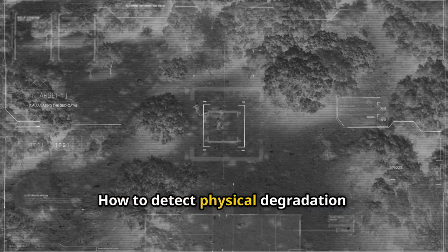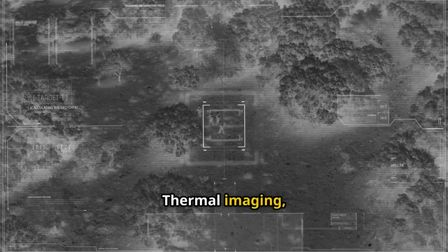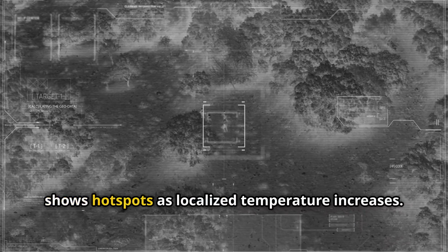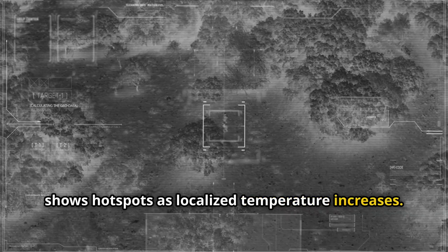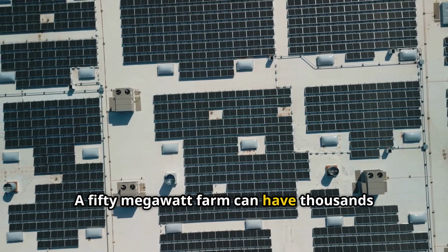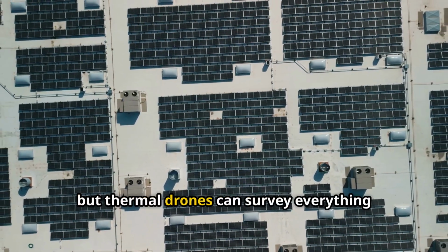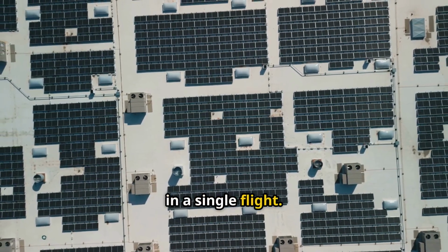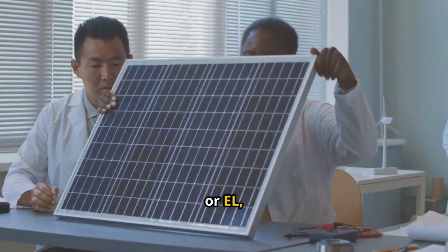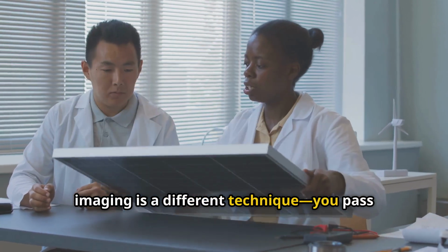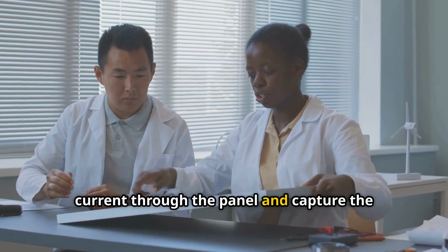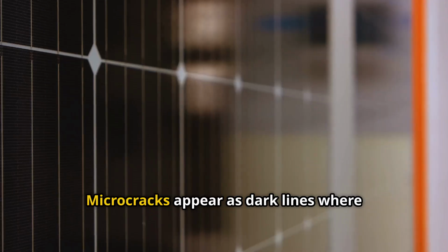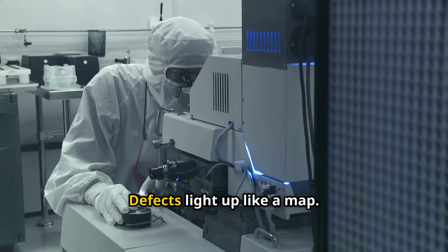How to detect physical degradation? Thermal imaging, or IR, shows hotspots as localized temperature increases. A 50-megawatt farm can have thousands of modules, but thermal drones can survey everything in a single flight. Electroluminescence, or EL, imaging is a different technique. You pass current through the panel and capture the light it emits. Microcracks appear as dark lines where current flow is interrupted. Defects light up like a map.